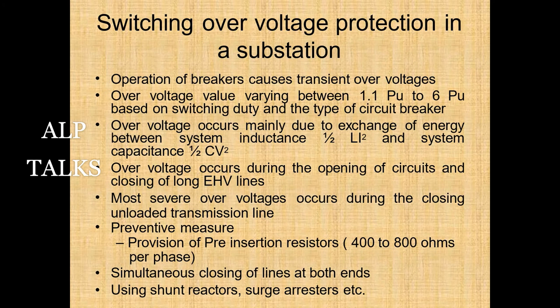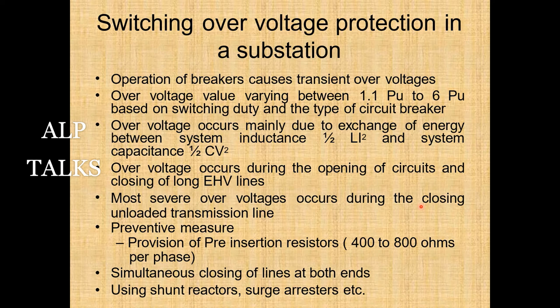Switching overvoltage protection: operation of breakers causes transient overvoltages varying between 1.1 and 6 times the normal voltage depending on switching duty and circuit breaker type. Overvoltage occurs mainly due to exchange of energy between system inductance (LI²) and system capacitance (CV²). Overvoltages occur during opening of circuits and closing of long EHV lines. Most severe overvoltages occur during closing of unloaded transmission lines. Preventive measures include provision of pre-insertion resistors of 400–800 ohms per phase, simultaneous closing of lines at both ends, and use of shunt reactors and surge arresters.